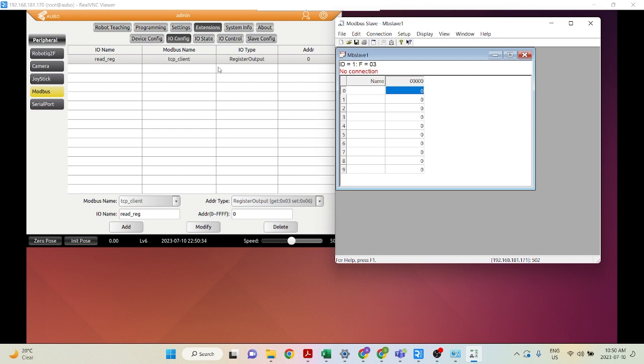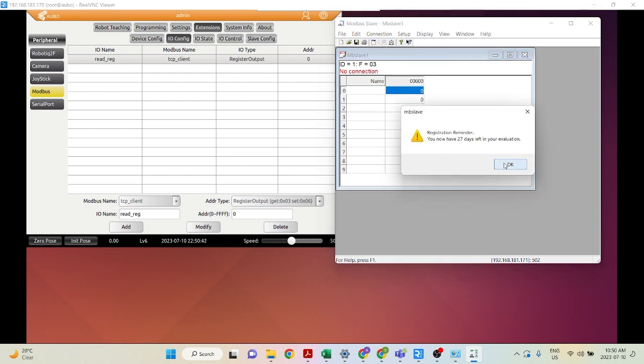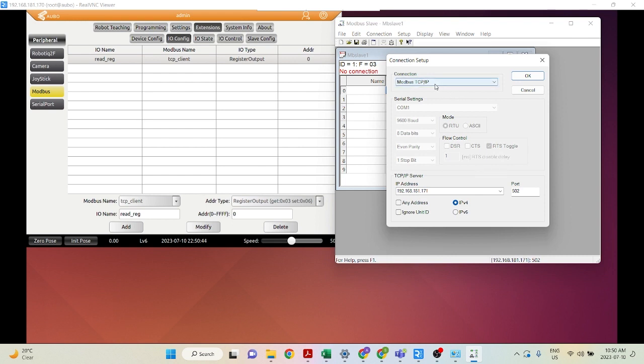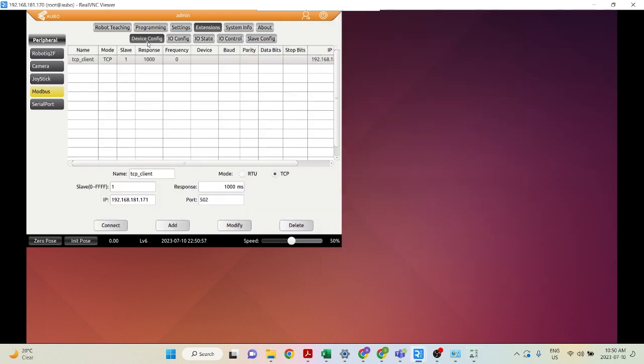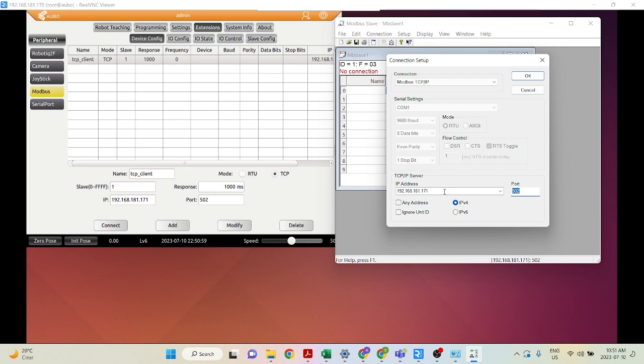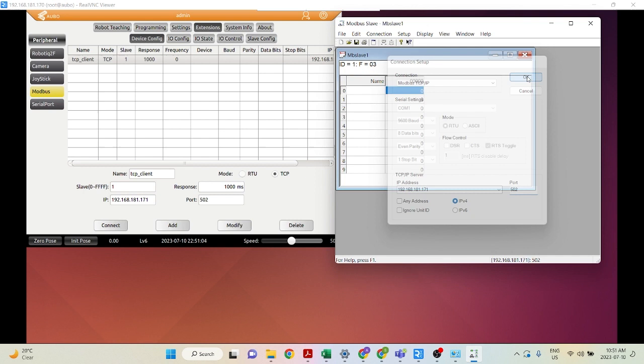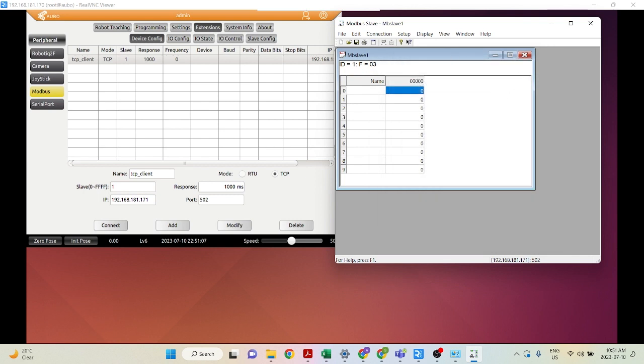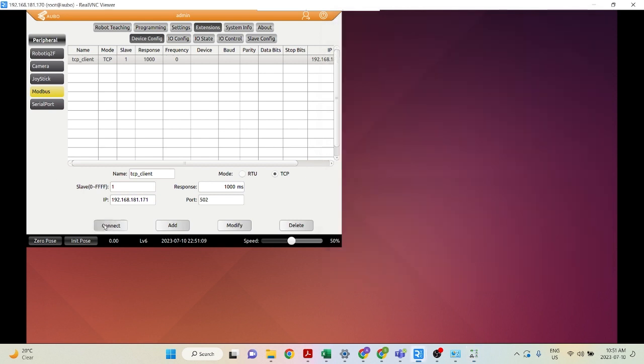Now let's configure our Modbus slave. Go into Connection and click Connect. Select Modbus TCP/IP as the connection type. Enter the IP address of your local computer, which is 192.168.181.171, and the port which we set as 502 under Device Config. We're using an IPv4 address. Click OK, and then click Connect — it should connect successfully.